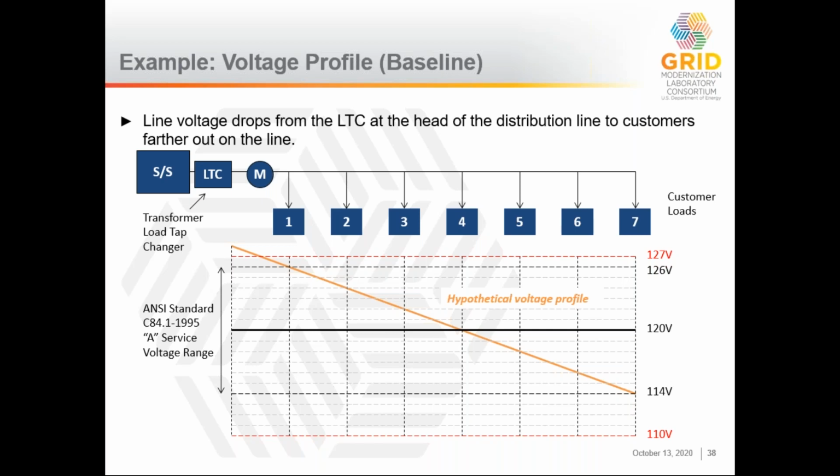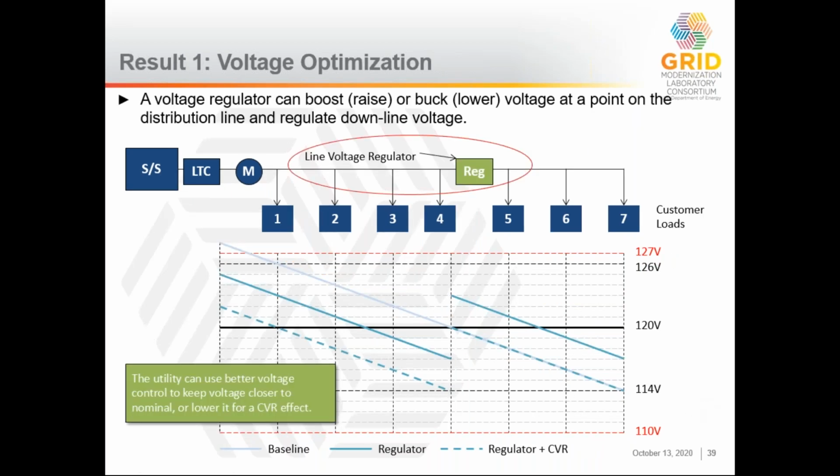But if you look to the next slide, you see how the distribution management system for voltage might be operating, where they have, say, line regulators in place, which will help bump the voltage in the middle of the line. Or there might be a capacitor sitting at the end of the line to boost the voltage over there as well. So just showing what a voltage profile actually looks like to give a little bit of a visualization of what you're seeing throughout the 3 days as well. So next set of slides.